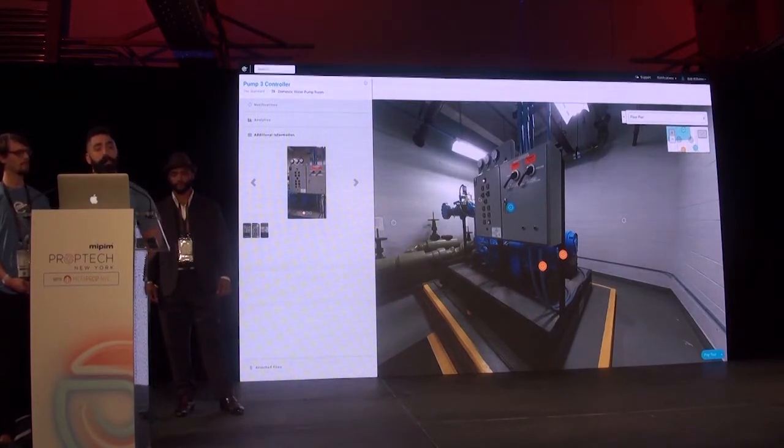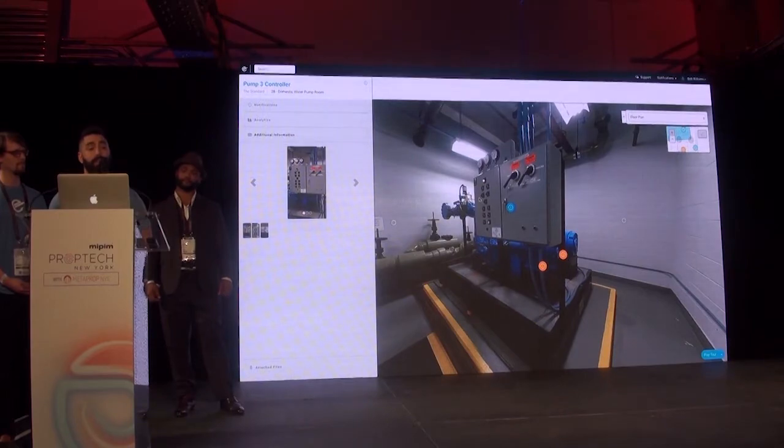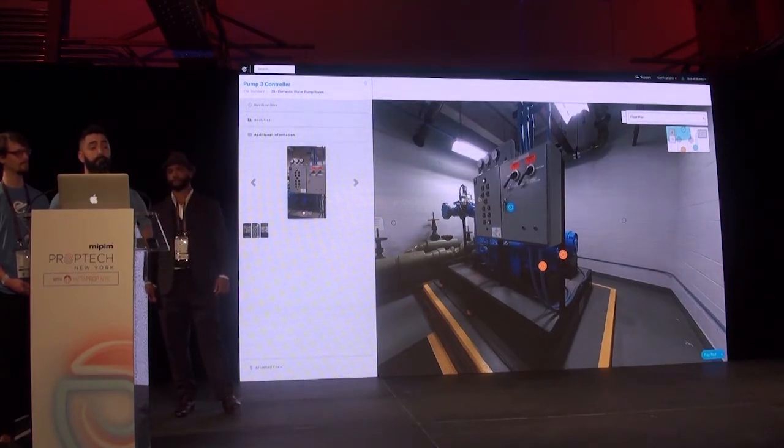In terms of a typical deployment for a 500,000 square foot asset, we might put in 15 of our own devices, each of which can monitor up to 42 pieces of equipment at the sub-second level. So we will deploy 400 to 600 sensors to monitor those systems. Again, that's 7 variables on power data, runtime hour data, dollar value from an empirical perspective.